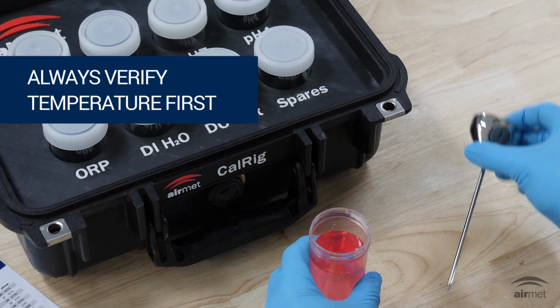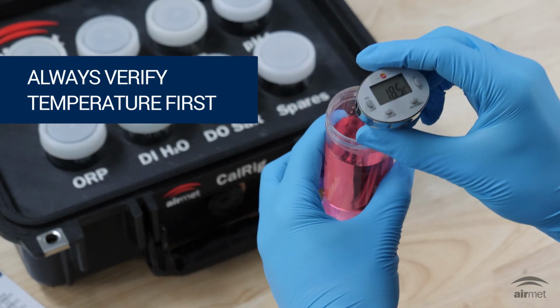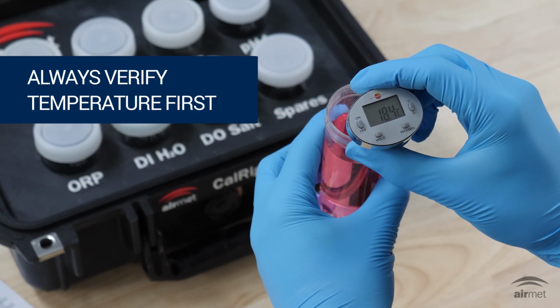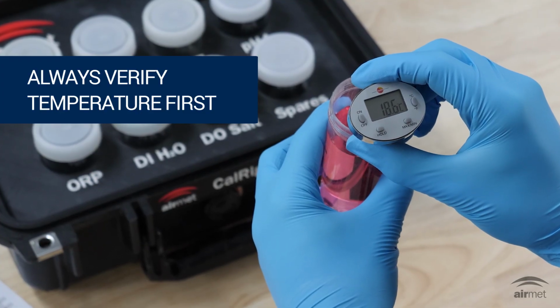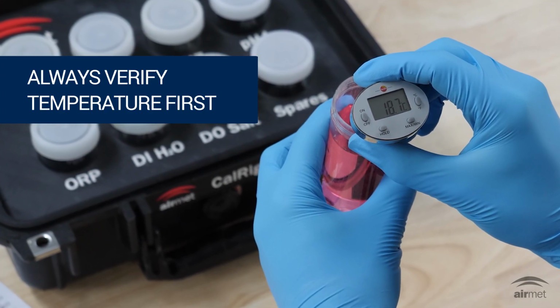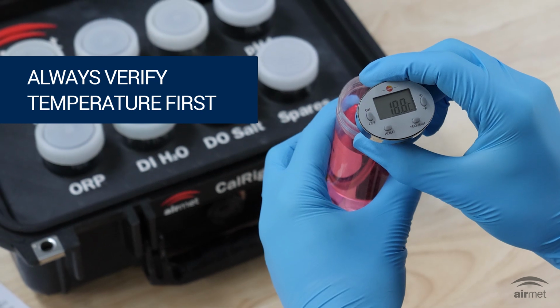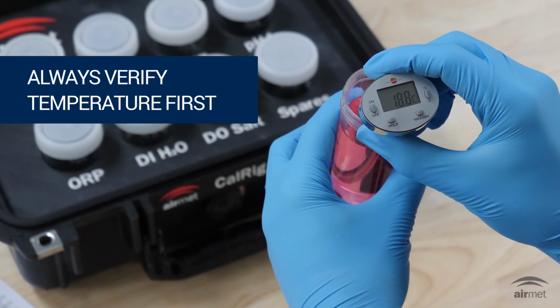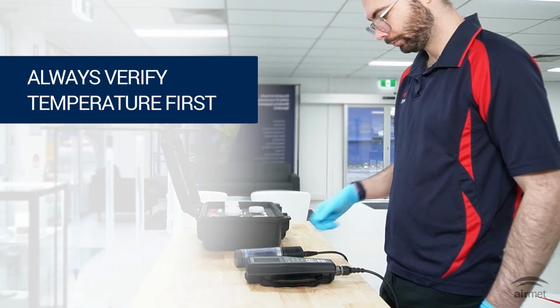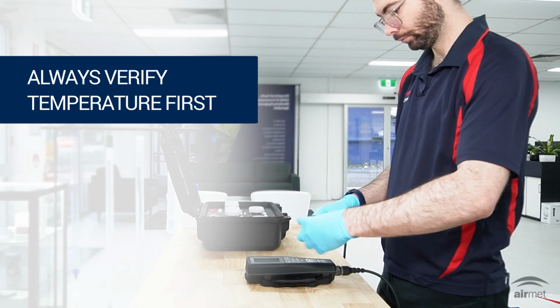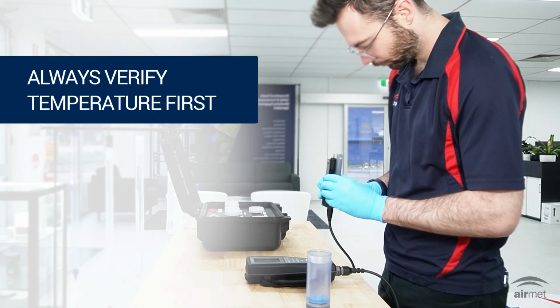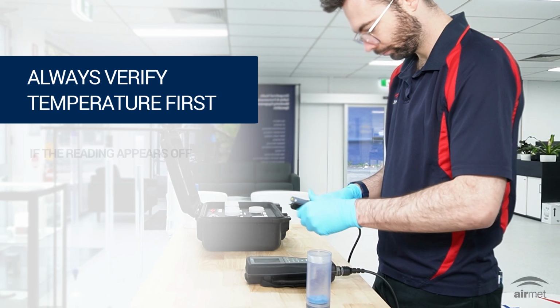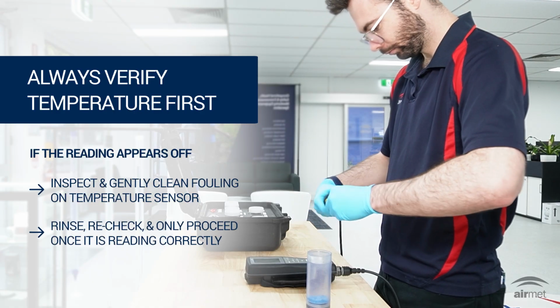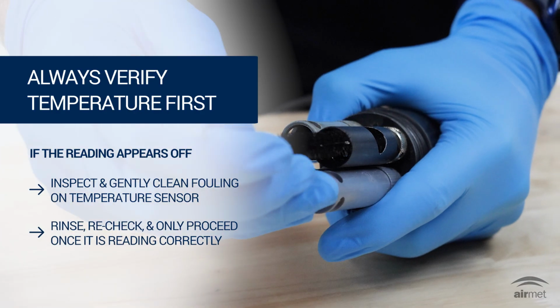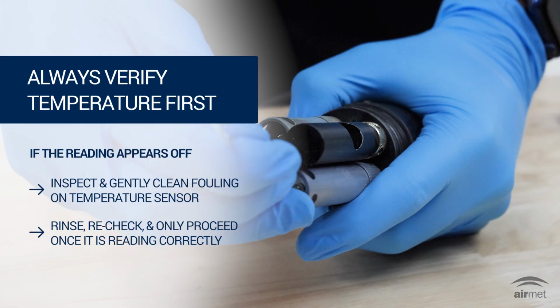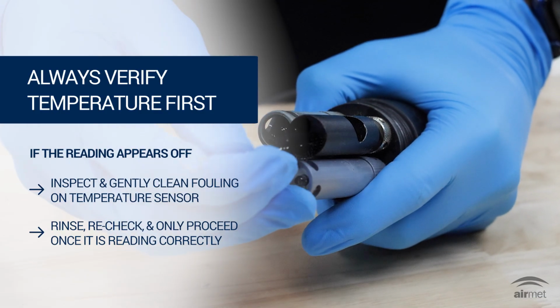Always confirm the temperature reading before any other calibration. Place the temperature sensor in a known reference, for example with a calibrated thermometer or a stirred water bath, and check that the reading is correct. Every other parameter uses temperature compensation, so an error in temperature will affect the overall measurements. The ProQuatro temperature sensor is factory set and not user calibrated, and normally does not need calibration. If the reading appears off, inspect and gently clean any fouling on the temperature sensor, rinse, recheck, and only proceed once the reading is correct.